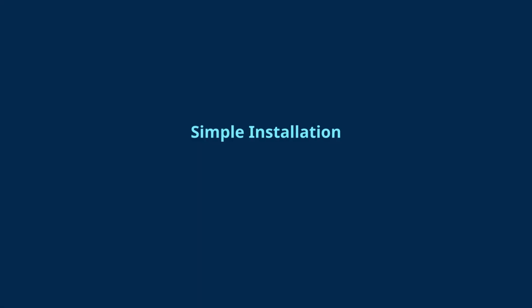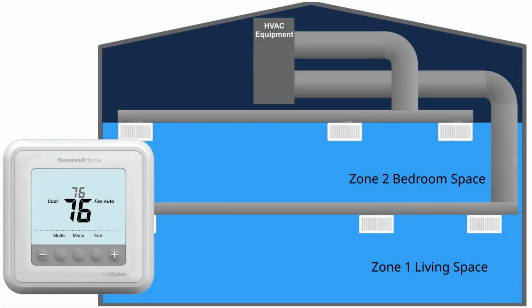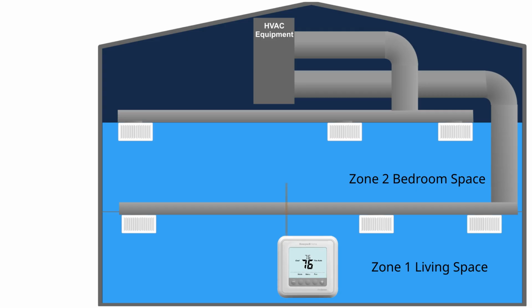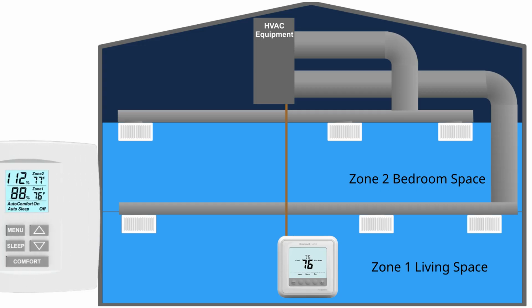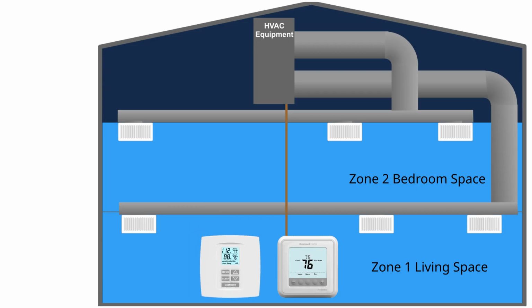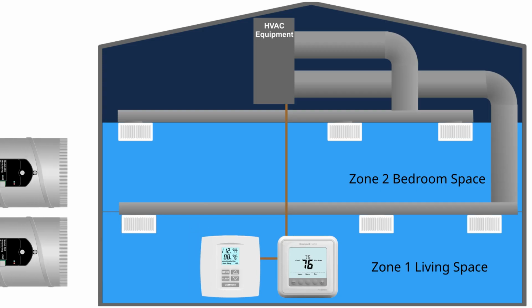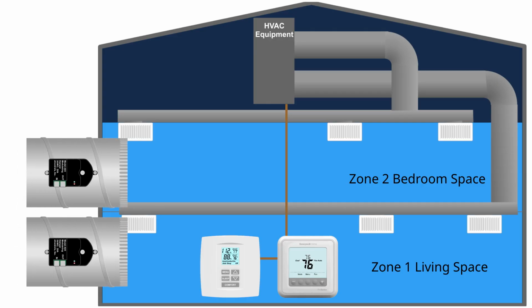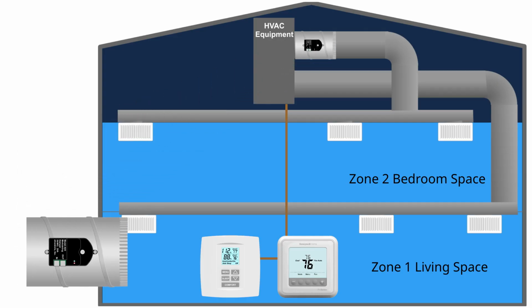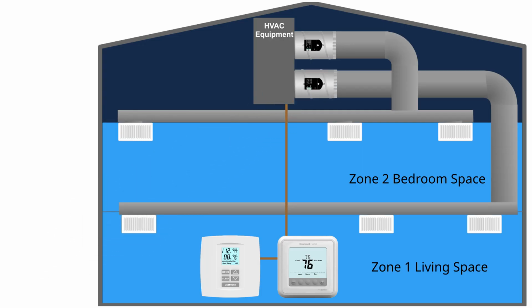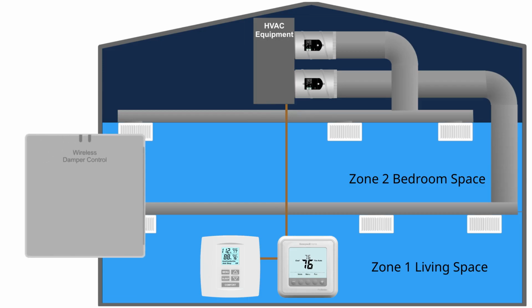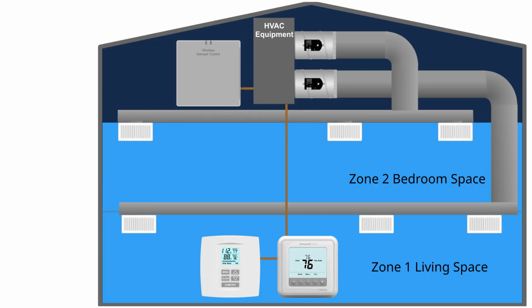Let's take a look at the simple installation. Any 24 VAC thermostat is installed and wires to the equipment. The two-zone comfort control is typically installed in the downstairs zone and connects to the thermostat for 24 VAC power. 2 modulating plug-and-play dampers are installed, one in the trunk feeding the upstairs zone and one in the trunk feeding the downstairs zone. The damper control module is installed near the equipment, and 4 wires are used to connect to gas electric or heat pump equipment to power the damper control and to monitor heating and cooling calls.